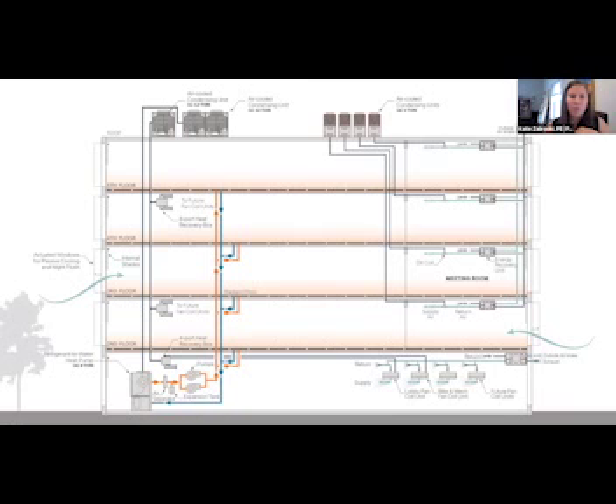On our roof we have air-cooled condensing units that transfer energy between the ambient air and refrigerant. That's routed down into a refrigerant-to-water heat pump in our mechanical room, which transfers energy between the refrigerant and hot or chilled water, distributed through the building to radiant slabs. We use radiant slabs to heat and cool the space, and that does the bulk of the heating and cooling.